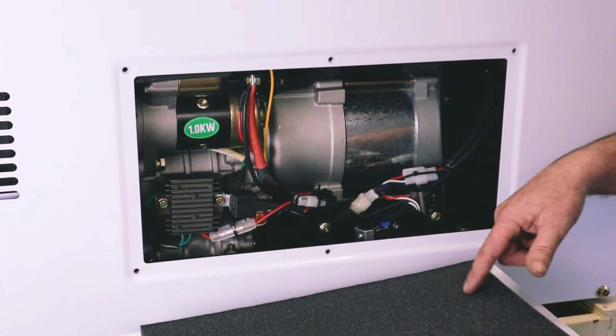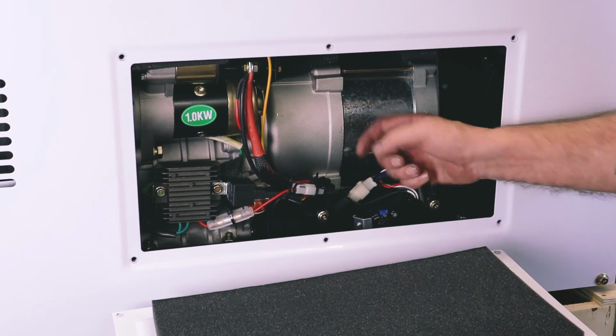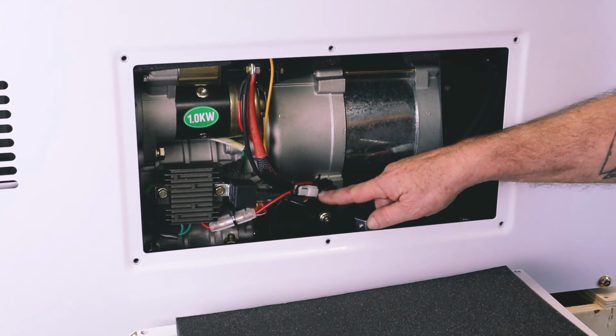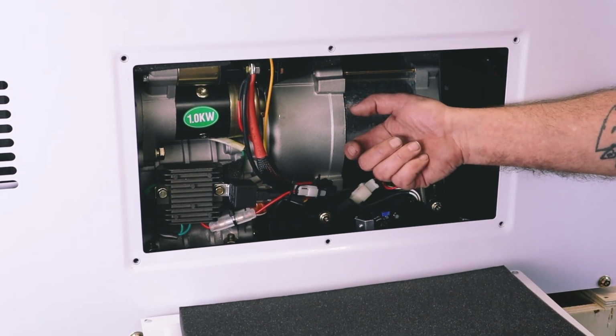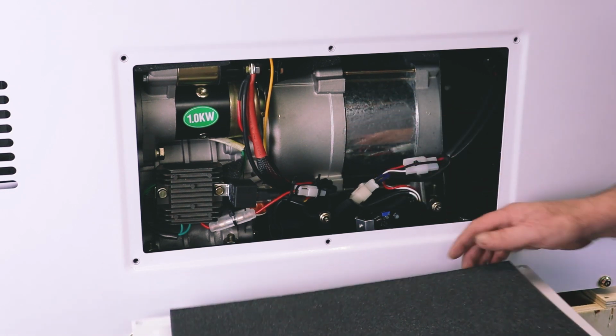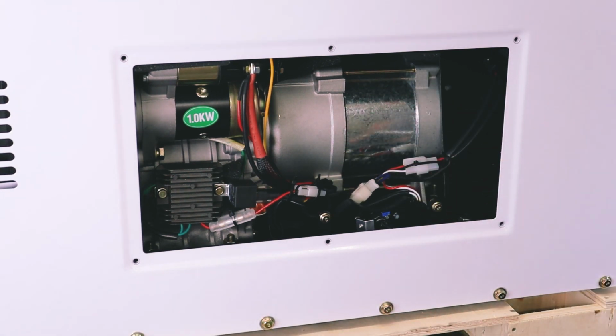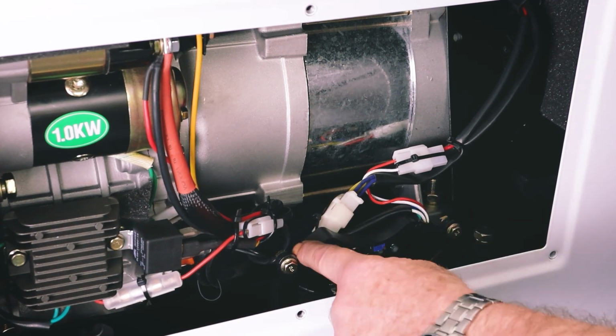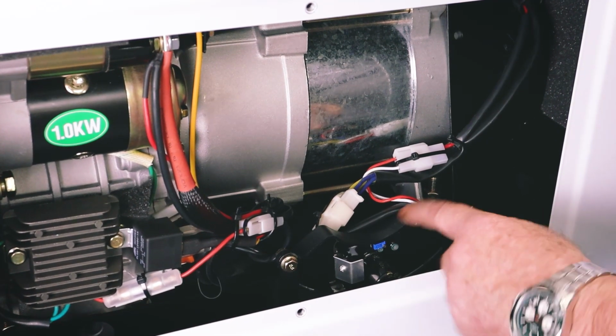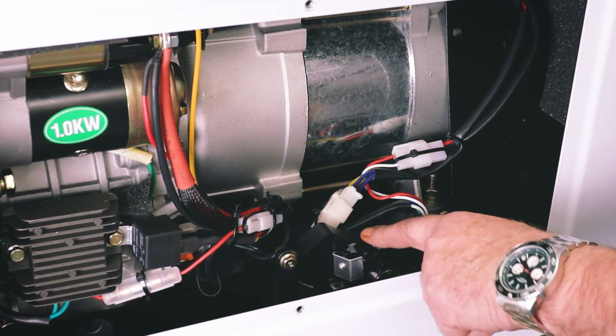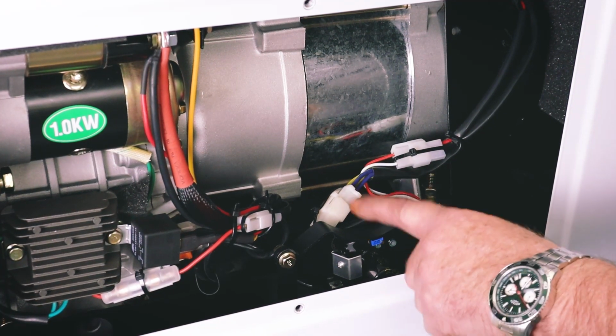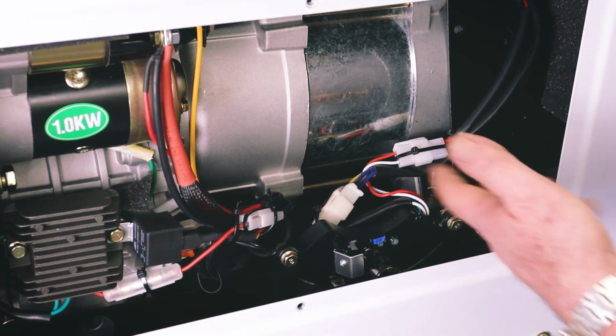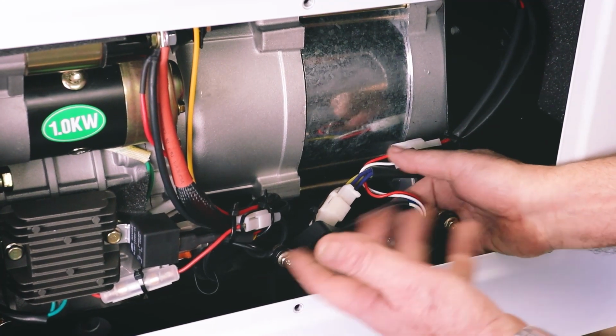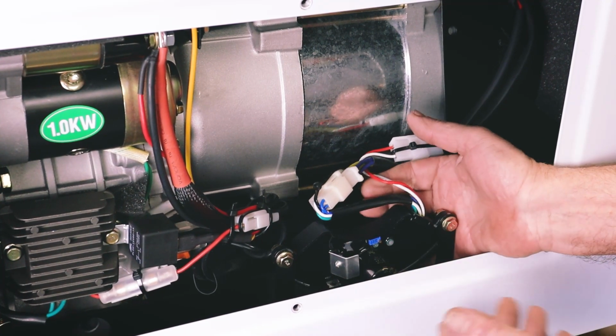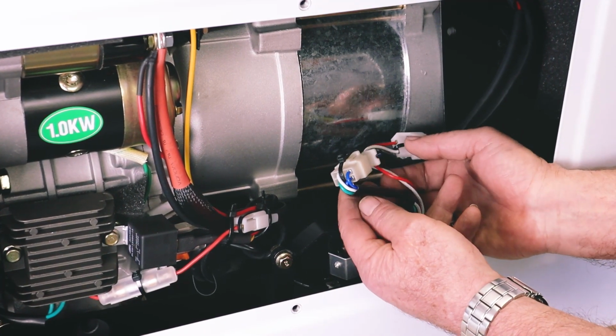Now, if yours does have the fan in it, you'll find a connector plug in here. There will be a cable tie such as these around the connector plug. You can just cut it, disconnect the connector plug, and take this cover away. So the AVR is this horseshoe-shaped plastic unit here with the components on it. This is what we suspect to be wrong at present. So first thing is a visual. Does it look like it's burst? There's problems with it, scorch marks, that sort of thing. Does all the wiring look intact?